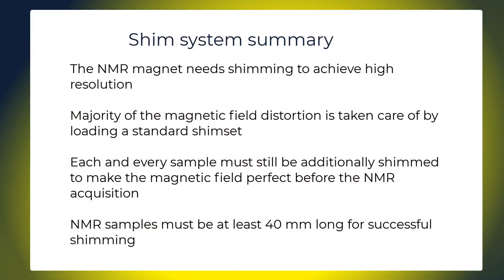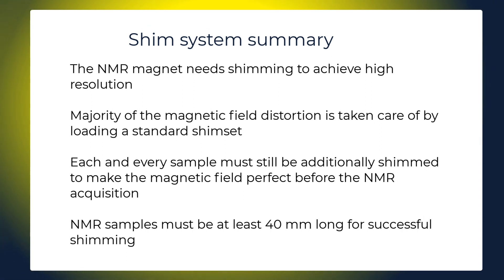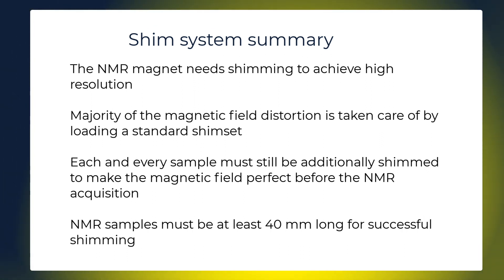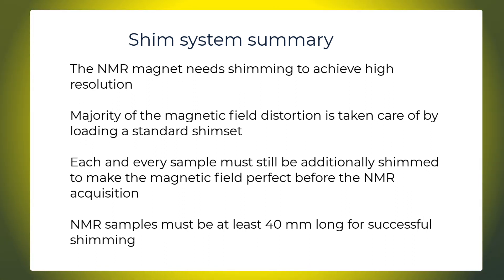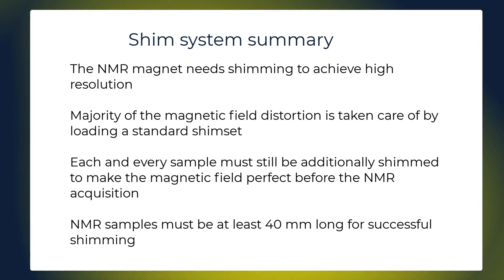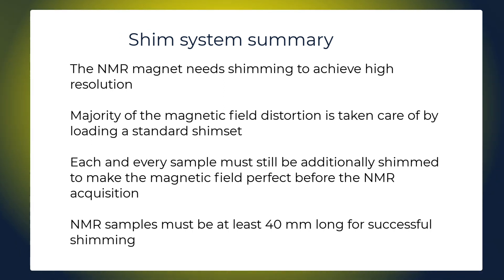In summary, the NMR magnet needs shimming to achieve high resolution. Majority of the magnetic field distortion is taken care of by loading a standard shim set. Each and every sample must still be additionally shimmed to make the magnetic field perfect before the NMR acquisition. NMR samples must be at least 40 mm long for successful shimming.